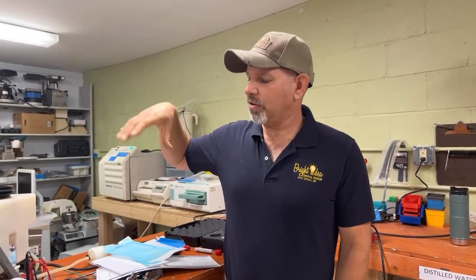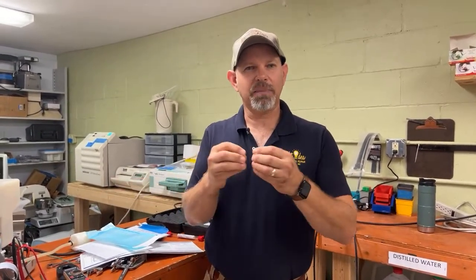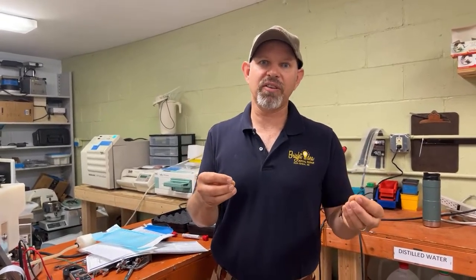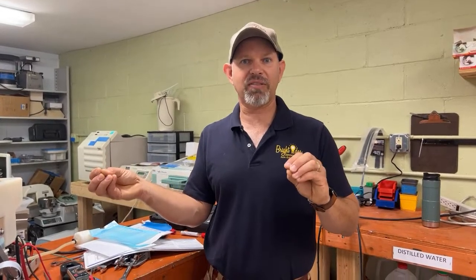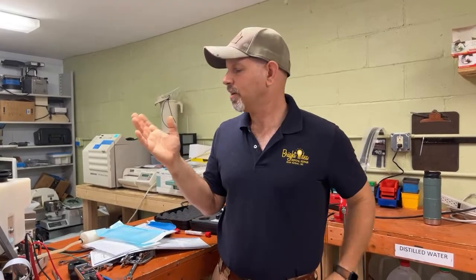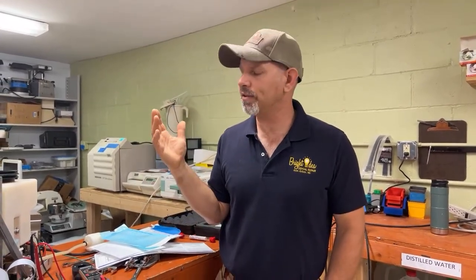Every single component, this is actually the question: why do we need to calibrate this? Every single component has a slight difference in resistance and how it responds, even if it's just a little one. You might have a wire that has just a little bit more or less resistance than the other wire. There might be a connection that's not quite as good, with a little bit more resistance on that connection. So that's affecting the voltage going through it. Ohm's law has voltage, current and resistance. Those three things affect everything about how these work. More resistance is going to mean less current.